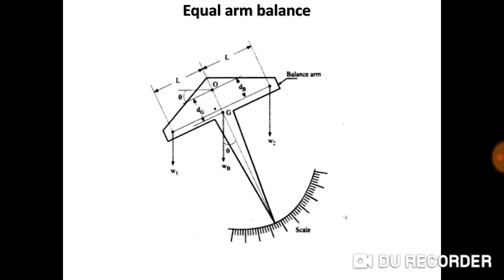In an analytical balance, a long pointer is attached at right angles to the beam at the fulcrum and indicates zero on a scale when the beam is parallel to the ground level. The balance arm rotates about the point O, and two forces W1 and W2 are applied at the ends of the arm. W1 is an unknown force, whereas W2 is a known force, that is a standard mass. Point G is the center of gravity of the balance arm, and Wb is the weight of the balance arm and the pointer acting at G.